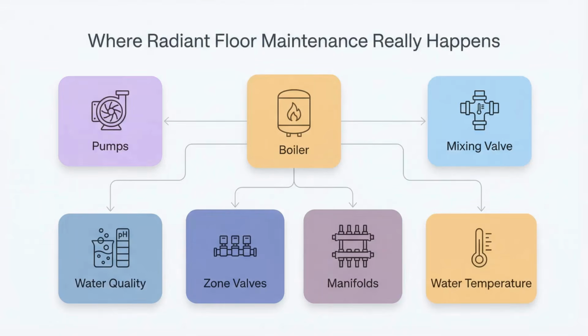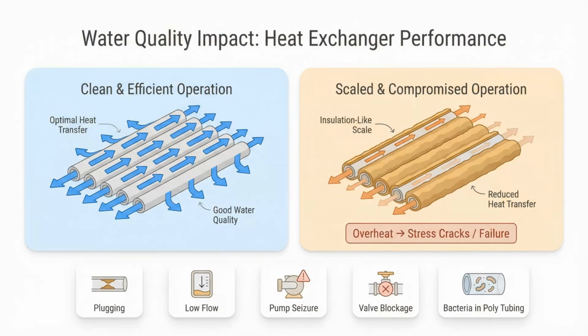For radiant floor heating systems, most maintenance centers on the boiler and the components around it: pumps, mixing valves, zone valves, and manifolds, plus water quality and water temperatures. Many modern components are designed for long life with minimal service, but the system still depends on correct conditions, especially clean, treated water. Water quality is described as the most important servicing factor. Untreated water drives oxidation of ferrous materials and sediment buildup that can foul pumps, mixing valves, zone valves, manifolds, and heat exchangers. Scale inside the heat exchanger reduces heat transfer, like insulation, which can overheat the exchanger and lead to cracking or failure.